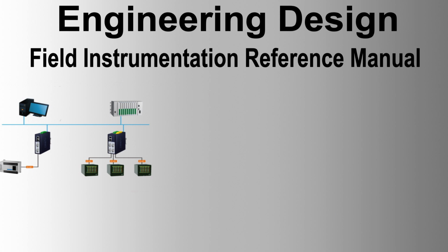Optical flame detectors. Optical flame detectors use sensors to detect the light emitted by a flame. They can include UV, IR, or visible light sensors. Applications. Commonly used in industrial settings, refineries, and chemical plants for fire detection. Advantages. Provide fast and accurate flame detection with a low rate of false alarms. They can detect flames through smoke and dust. Limitations. Optical flame detectors require a clear line of sight to the flame and can be affected by environmental factors such as sunlight and hot surfaces. Regular maintenance and calibration are necessary.